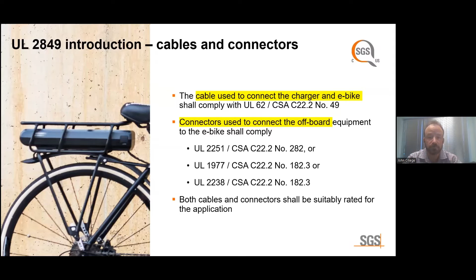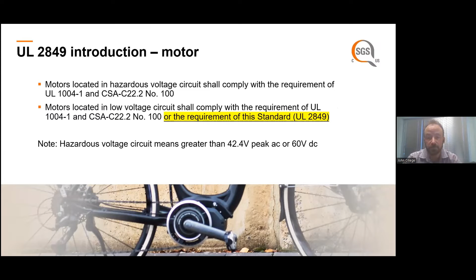Then we look at the motor. Motors in a hazardous voltage circuit are required to be certified to UL 1004. If they're in a low voltage circuit, they may or may not be certified to 1004. If they're not certified to 1004, then we would test them to the requirements within UL 2849. A hazardous voltage circuit is defined as a circuit greater than 42.4 volts AC or 60 volts DC. Now, the motor controller and the BMS are both considered safety circuits or protective circuits. A circuit is defined as a protective circuit if it's considered critical to mitigate fire, electric shock, or explosion hazard.